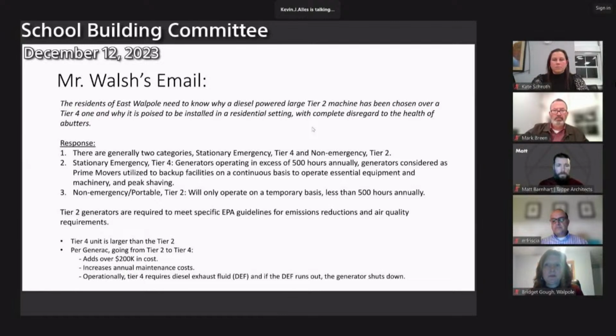Again, in a single space by itself that doesn't break the bank. So it's going to be less load on the generator, but when you look at just the lighting load and the receptacle loads in those areas, it's not a lot. It's the mechanical systems, the elevator, the kitchen, the building management systems, the security systems, the fire alarm systems -- all as a culmination that adds up. So trying to isolate one single thing and say we could reduce the generator size or knock it back a little, it's not as easy as it sounds.